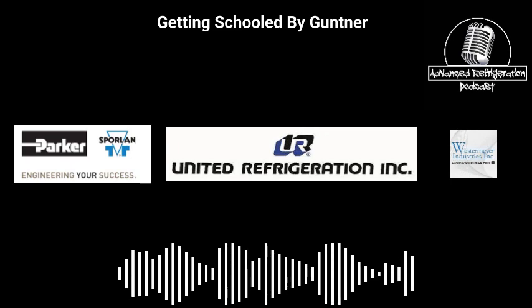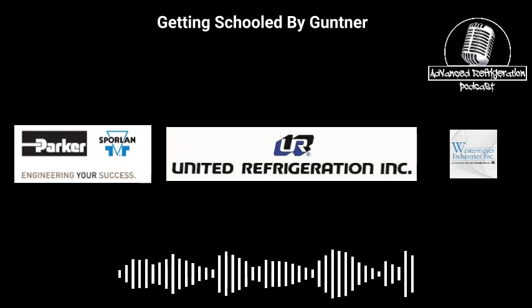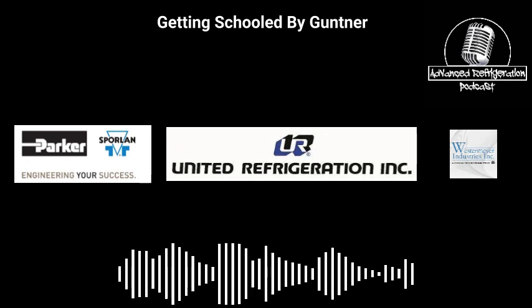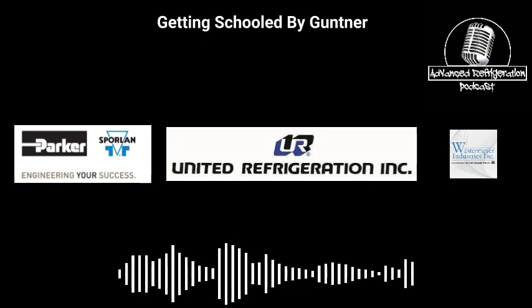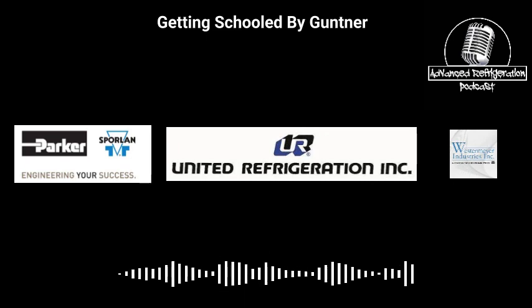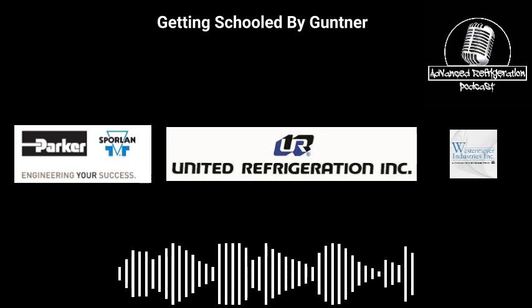This happens every single job, exactly what you said. Here's the problem: I do startup, and I generally don't come on site until they're ready to do startup. By that time they've already pulled vacuums, and I'm busy trimming out the EMS. You guys need to put a big old fat sticker on that header. I'm serious, that well must be brazed in. Yeah, that was a lot of it.